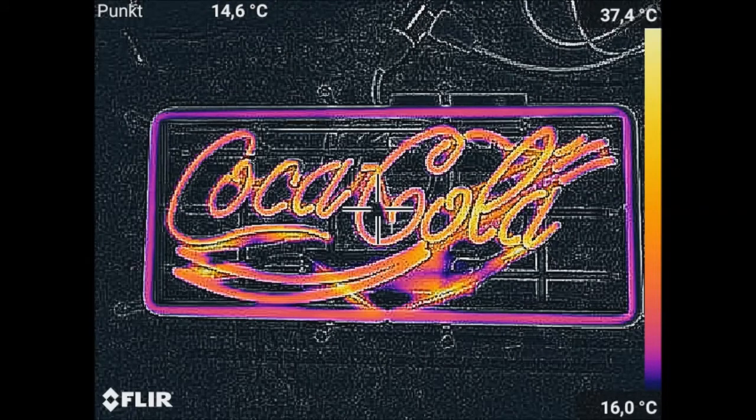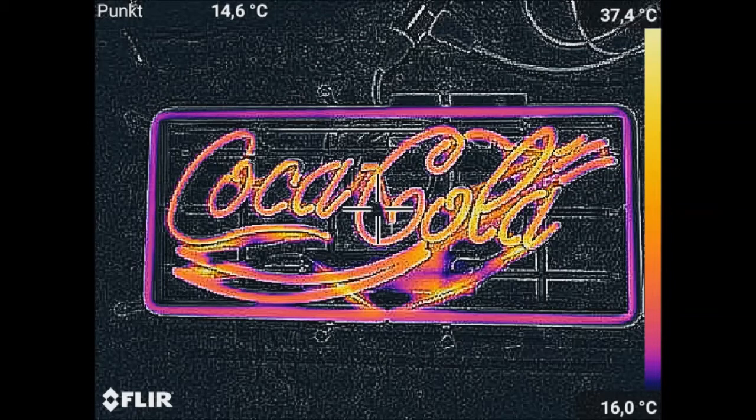When the electrodes are okay I take an overall thermal shot of the sign to see if one tube is much off the others in temperature. You must remember that smaller tube diameters on the same sign will be warmer and also red gas tubes will always be a bit warmer than the same diameter blue gas tubes. But everything looks fine here and I'll say the faulty part this time was just the transformer.